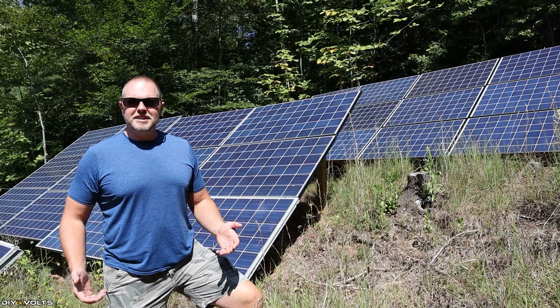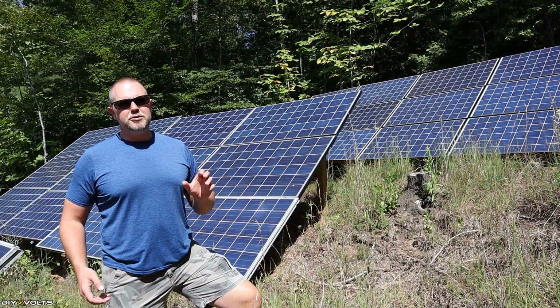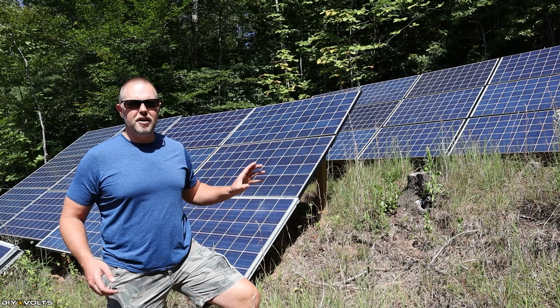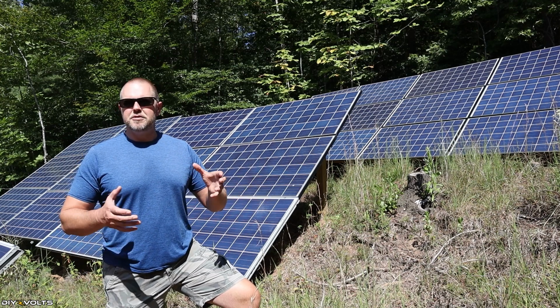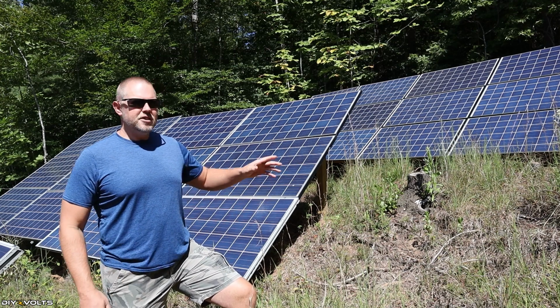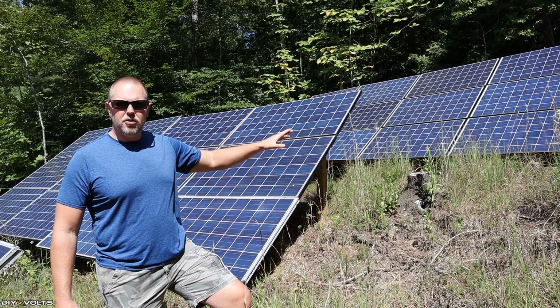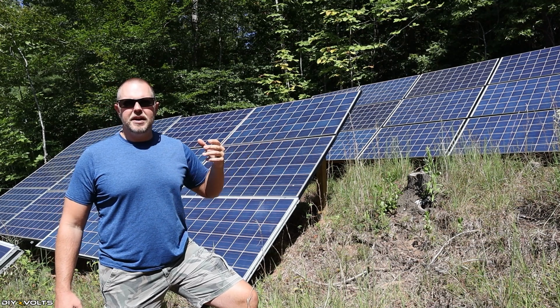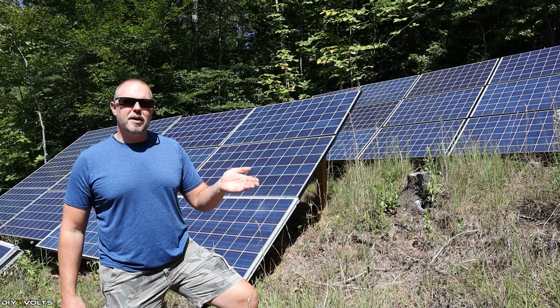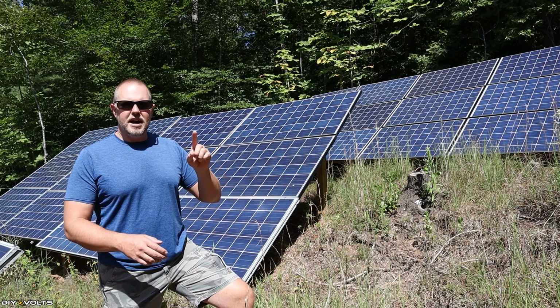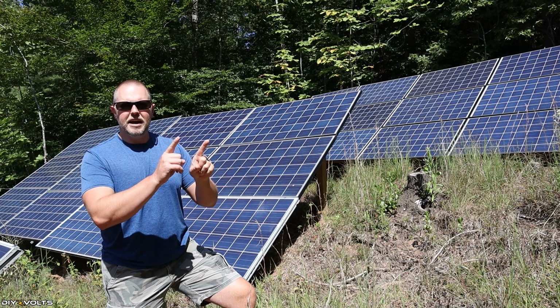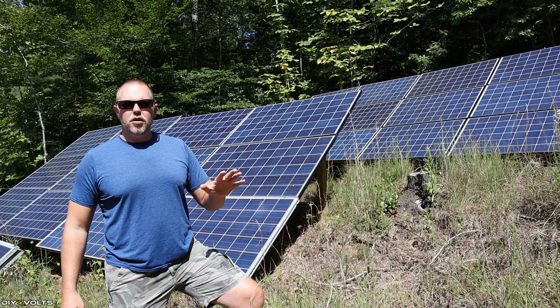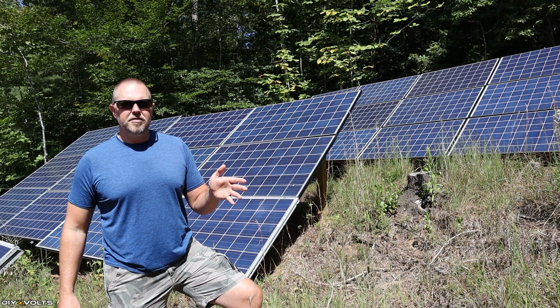The EG4 18K hybrid inverter can accept up to 600 volts per string of solar, and will use up to 500 volts of that. With my 12 panels per array linked in series — positive, negative, all the way to the end — I get one single positive and one single negative, for a voltage of somewhere around 400 to 450 volts.